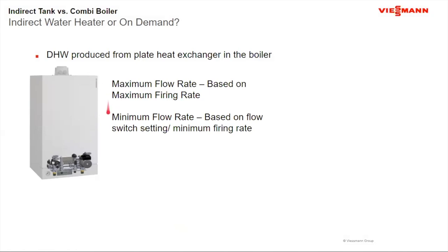On the minimum flow rate, first off, there's going to be a flow switch in there to fire it. It's normally going to be set at about a half to maybe 3/4 of a GPM. And a lot of this is tied to the minimum firing rate of the boiler. So if I'm going to do a half a gallon a minute, I have to get down to about 20,000 BTUs per hour to produce that kind of water flow rate. So that does play into it as well.